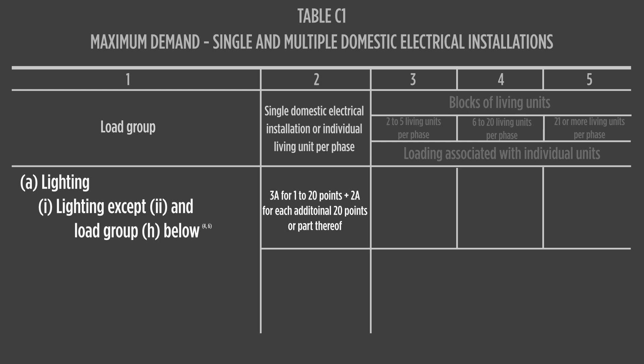How do you calculate the maximum demand in a single-phase domestic installation? Let's begin with our first load group: lighting. The notes attached to table C1 define a lighting point load as 60 watts. Table C1 allocates 3 amps for 1 to 20 lighting points, and 2 amps for every additional 20 points in a single domestic dwelling. With the introduction of energy efficient lighting, an equivalent loading can be obtained by dividing the connected load wattage by 60 to get the equivalent number of points for calculation.